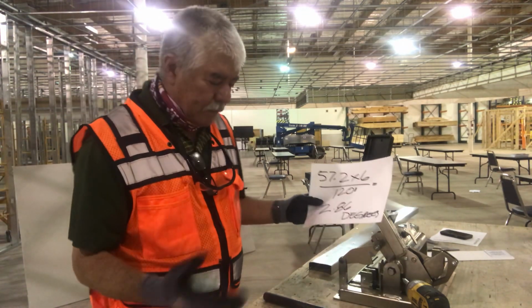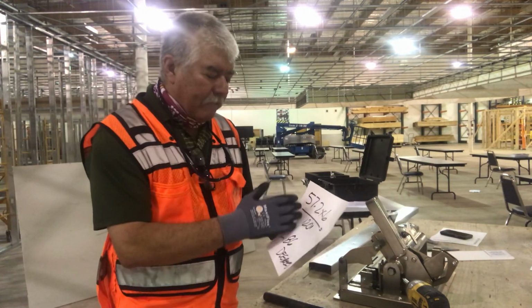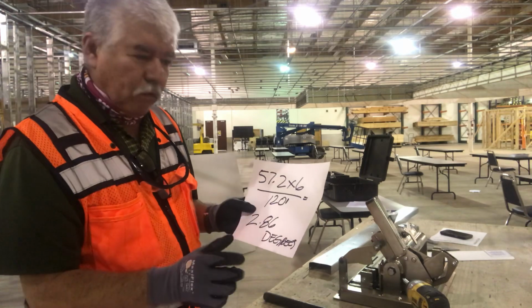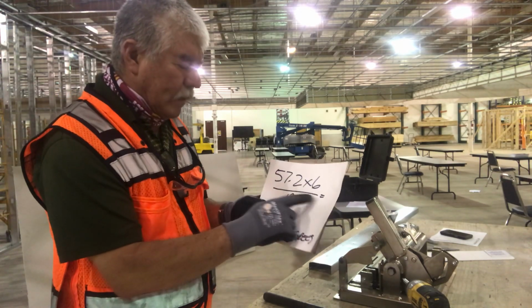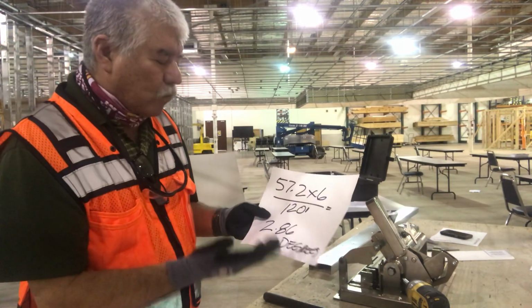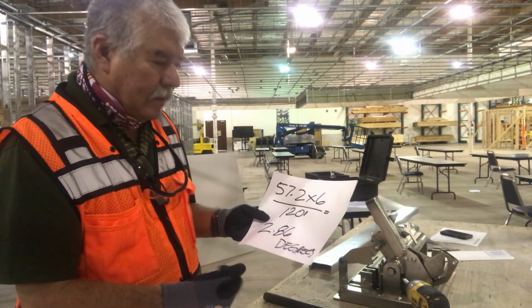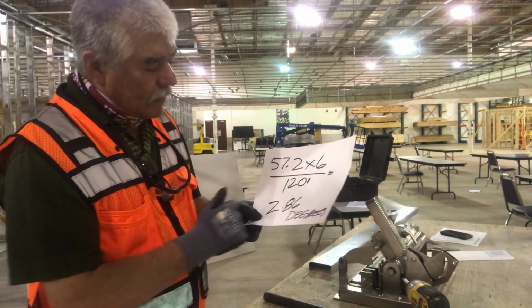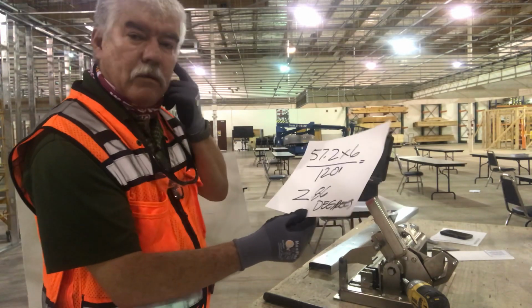So the formula is really easy: I'm going to multiply 57.2 times 6, and that equals the bending spaces. Whatever result we get, we divide by 120 inches. The result gives us 2.86 degrees.